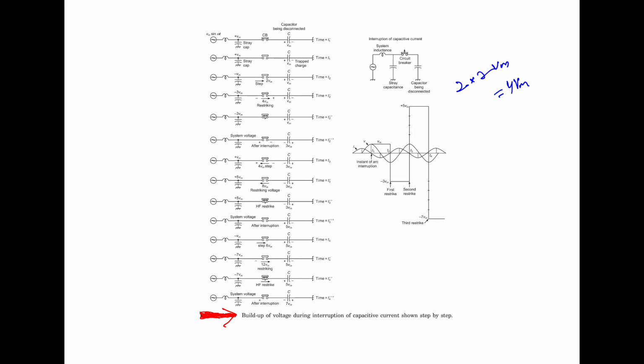Now, this high frequency discharge provides a number of current zeros. Eventually, the contact will recover, but in this process, there will be a charge transfer from the left hand side to the right hand side, leaving the capacitor C with the charge corresponding to the voltage of minus 3 Vm. Now, in the meantime, the LHS end of the circuit breaker contact continues its swing in synchronism with the system voltage, and it swings to plus Vm at the time t3.